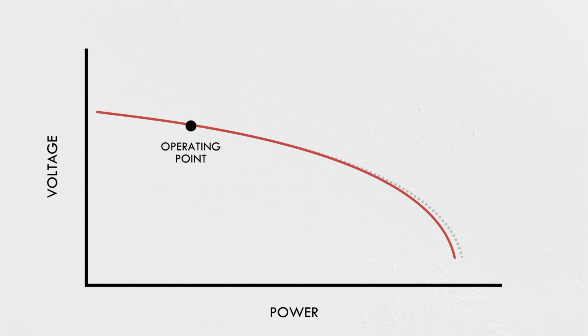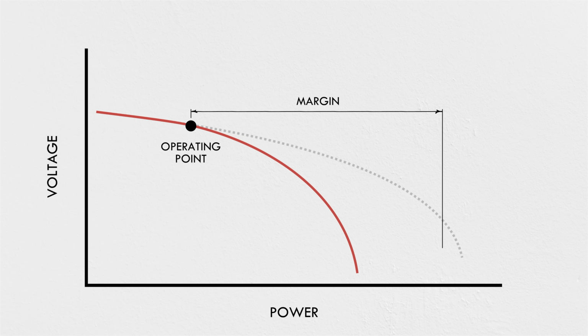Infrastructure is expensive, and building new power plants and transmission lines always comes with legal and environmental challenges too, so we're often forced to use the grid to the very limits of its capacity. But grid managers need to make sure to operate with enough margin that any contingency, like a generator going offline or a transmission line faulting, doesn't push the system over the electrical cliff. And here's where power factor comes in. Loads with lower power factor shift the nose of the PV curve down and to the left. That reduces the margin and lowers the voltages in the system for a given power demand, making voltage collapse more likely if some part of the system goes down.